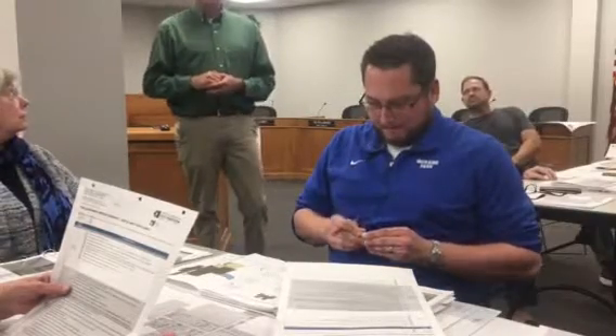Outside air is brought in to provide fresh air for building occupants. With old units, like those units, a lot of things go wrong and they don't function properly. We are looking at those units constantly to make sure that they're functioning the way they're supposed to. But if a damper hangs up on one of those units on a day when it's 20 below, those coils are going to freeze and they're going to burst. And the pumps are going to keep pumping, so we'll probably have 80 to 100 gallons per minute flowing into that room. So that's the concern.